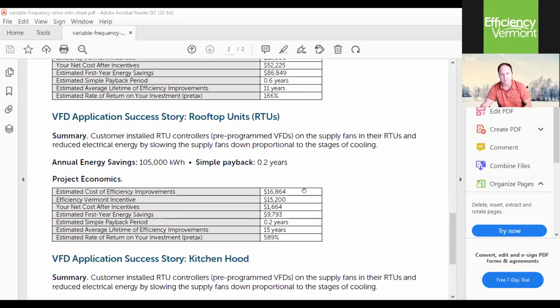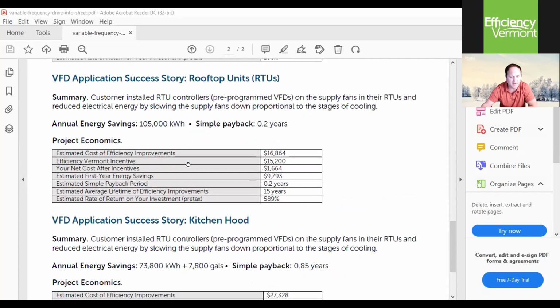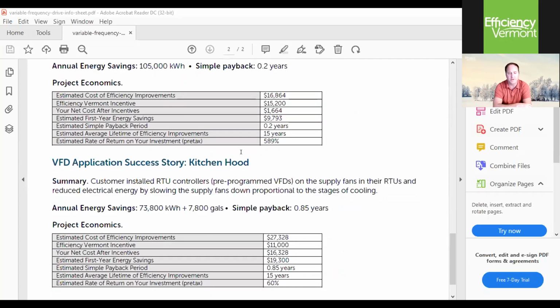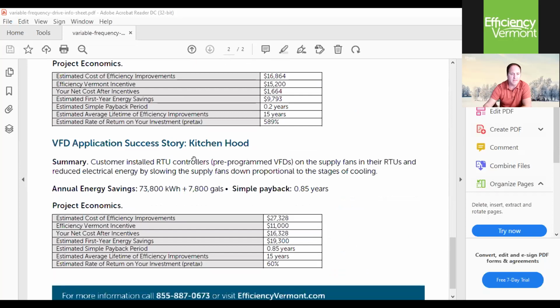Second example is a rooftop unit. This was a 0.2 year payback project. These are all on supply fans. And then finally, the kitchen hood, I alluded to this earlier. You'll see that there are really 2 saving streams here. There's a kilowatt hour saving stream, and then really, more importantly, a fuel oil or gas or whatever your heating source is, your heating fuel is. That's the big savings on a kitchen hood, which is indicative of really any exhaust fan.